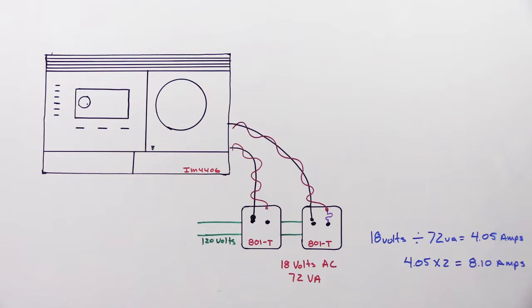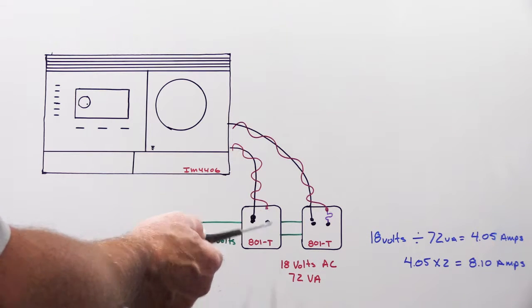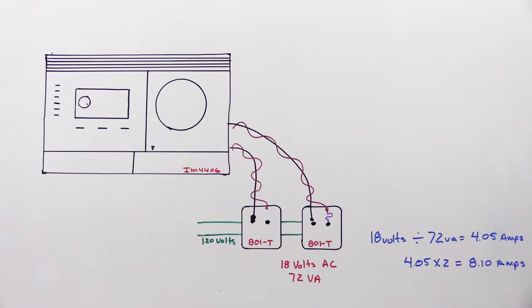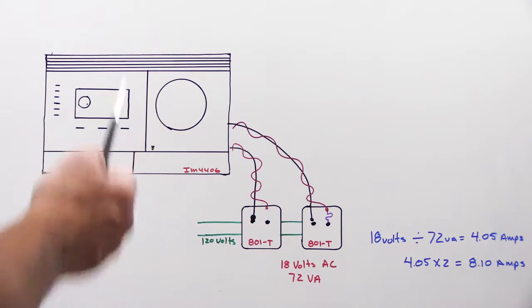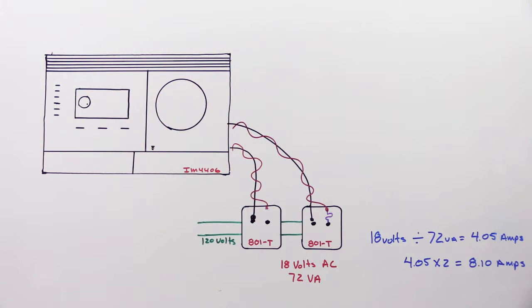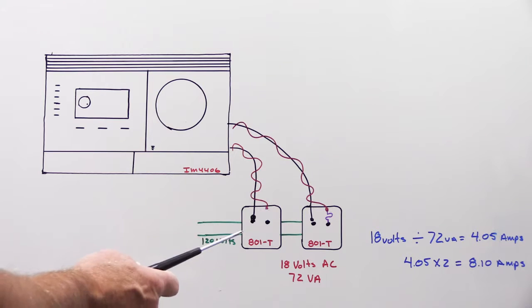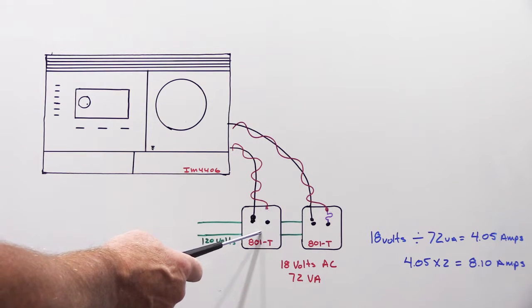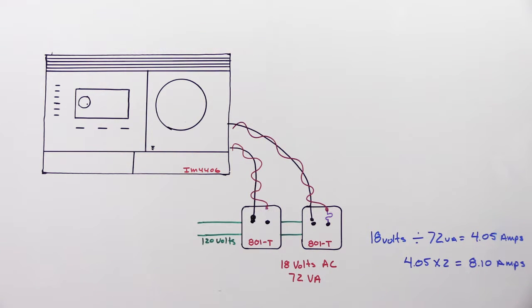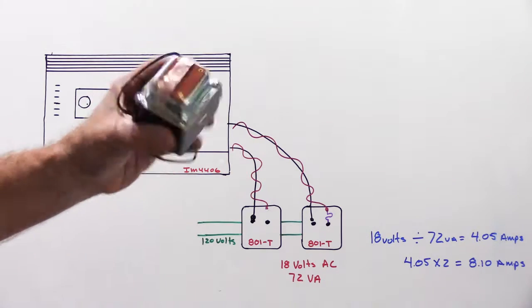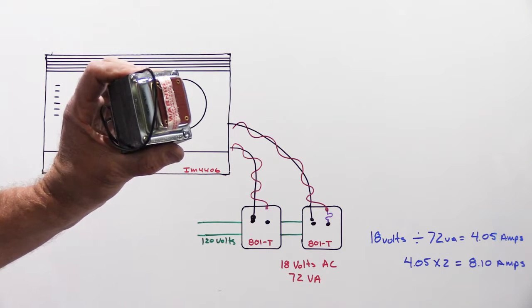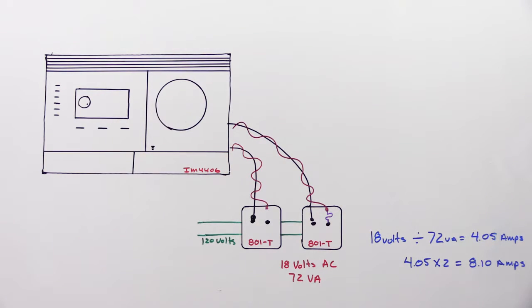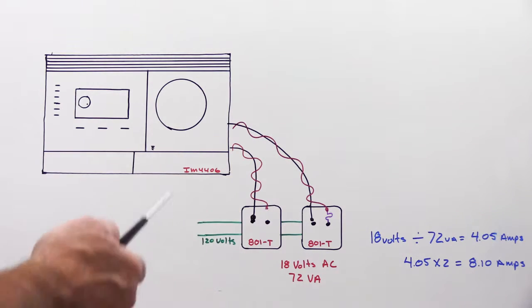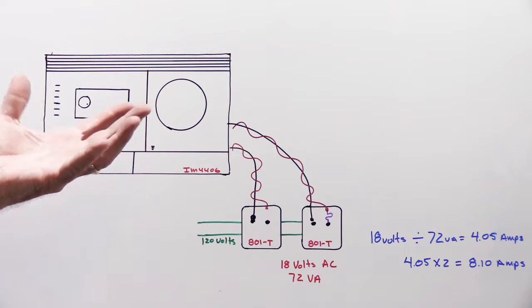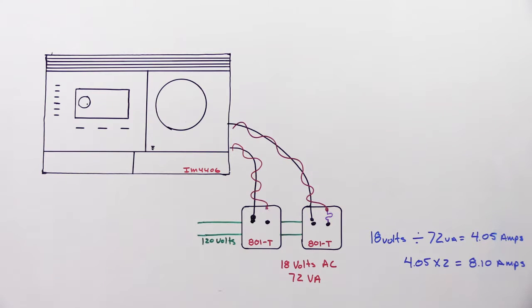So one of the things he needs to do is replace the one 801T with the blown fuse, because you have to have two working transformers to power the master station correctly. The dilemma is, what do you have to go through before you replace this to make sure that when you get a replacement, which is not inexpensive by the way, you don't simply install it, hook it up, and immediately blow the fuse again because there's a fault in the master station?